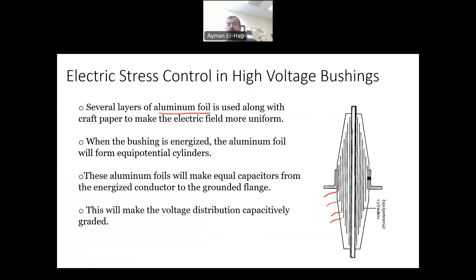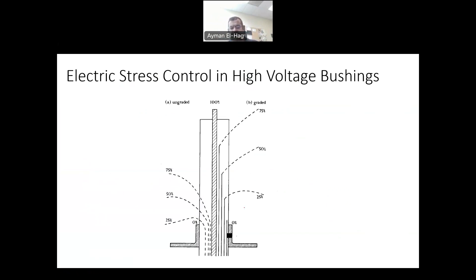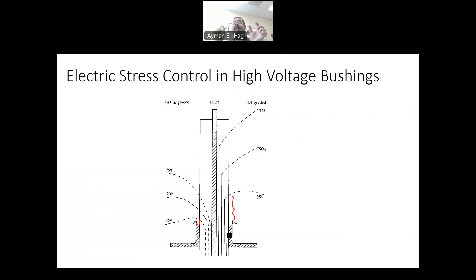Looking at the electric field distribution: on the right, a bushing with aluminum foils inserted; on the left, equipotential lines without those elements. Without foils, the distance between the zero-potential and 25-percent equipotential lines is much smaller. With foils, there is much more distance for the voltage to change, reducing the electrical stress. These are the two most common commercially available techniques to control the electric field inside a bushing.